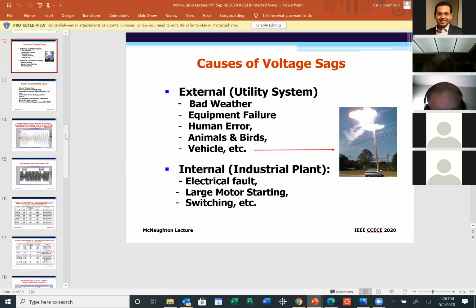Equipment failure is not uncommon. Human error: sometimes maintenance people operating at the utility substation could cause a problem. Animals and birds are one of the most common causes, where an animal gets into the electrical room and eats the insulation or whatever, and causes these failures. Car accident, I thought I'd share this picture with you. You hear of cars and trucks hitting a pole and causing a flashover, and this flash will result in voltage sags. Sometimes these events are internal to the industrial plant, like an electrical fault within their switchgear, or large motor starting and switching.